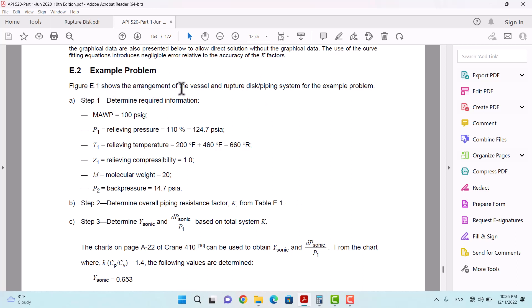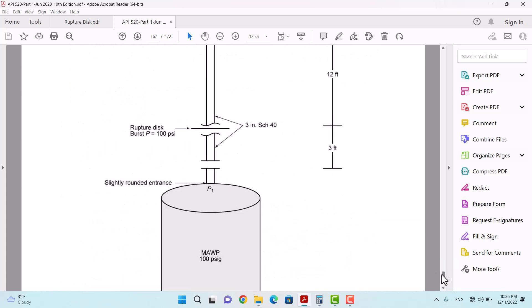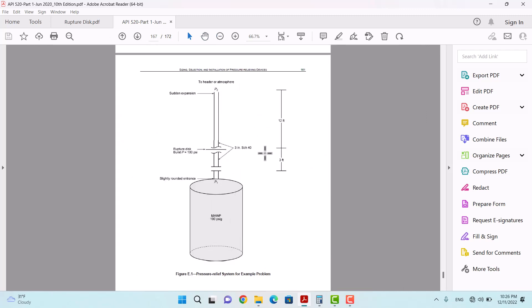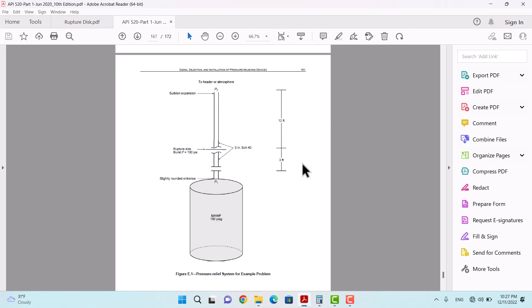Figure 1 shows the arrangement of the vessel and rupture disk piping system for the example problem. There is a vessel and a rupture disk. The burst pressure is 100 PSI, the piping diameter is 3 inches with schedule 40. The length from the flange to the rupture disk is 3 feet, and from the rupture disk to the header or atmosphere is 12 feet, so the total distance is about 15 feet.